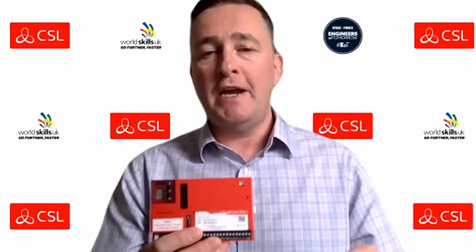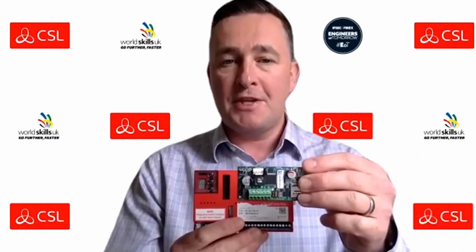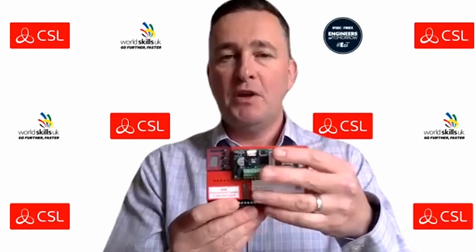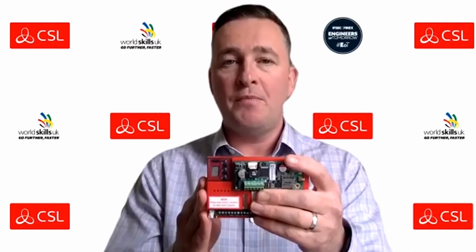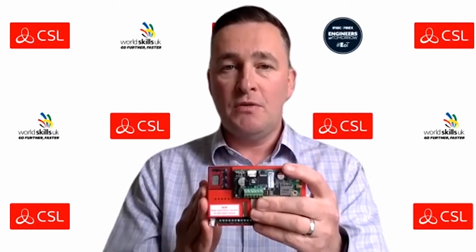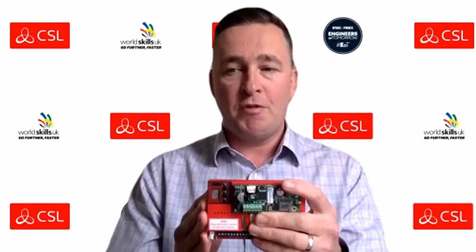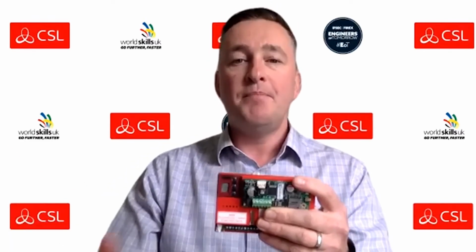So when we talk about dual radio, what we now do is we introduce a second 4G module with another roaming SIM on a completely separate and diverse roaming platform. So when we put these 2 modules together, you've now got DualPath alarm signaling at all grades without any wires whatsoever. So this now means that you can do an installation that's not reliant on any existing infrastructure, so you don't have to worry about network points, ports, firewalls, IT managers, etc. And you don't have to worry about the removal of PSTN.